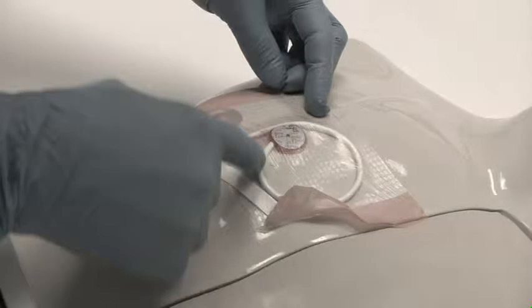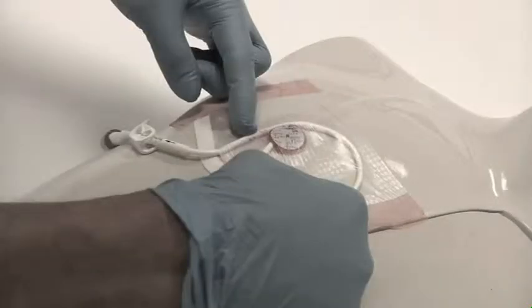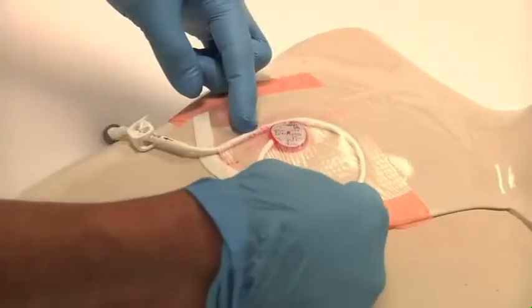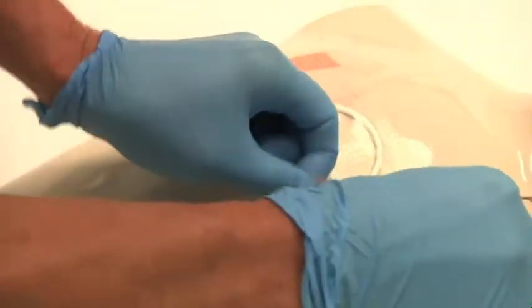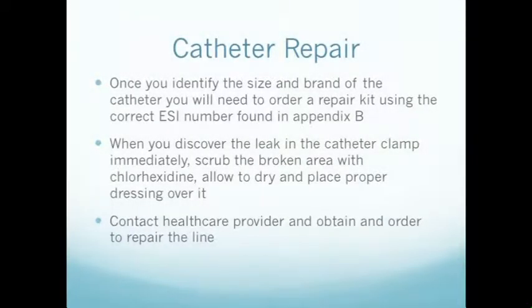Measure the length of the catheter from insertion site to the broken segment to make sure you have at least 5 centimeters of catheter in order to successfully perform the repair. Identify the type and size of the catheter. You must have an identical repair kit. You may order the repair kit by using the ESI number found in Appendix B.